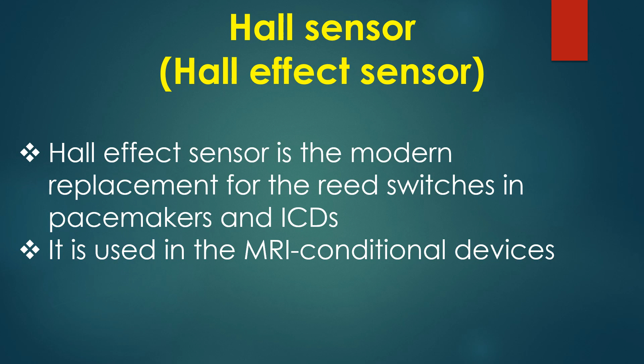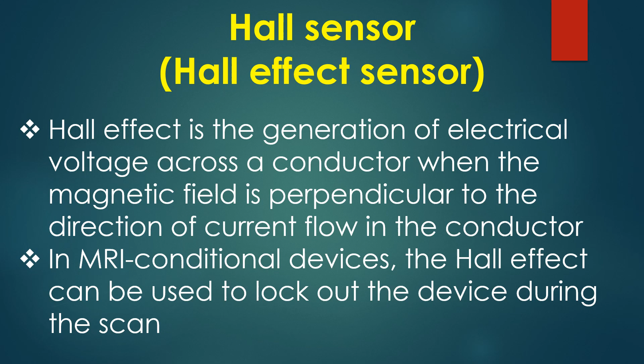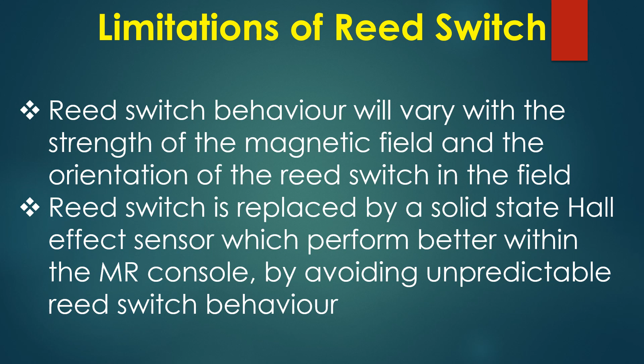Hall effect is a generation of electrical voltage across a conductor when the magnetic field is perpendicular to the direction of current flow in the conductor. In MRI conditional devices, the Hall effect can be used to lock out the device during the scan. Limitations of reed switch. Reed switch behavior will vary with the strength of the magnetic field and the orientation of the reed switch in the field. Reed switch is replaced by a solid state Hall effect sensor which perform better within the MR console by avoiding unpredictable reed switch behavior. Discussion on MRI conditional pacemakers including safety of 1.5 Tesla and 3 Tesla MRI scans.